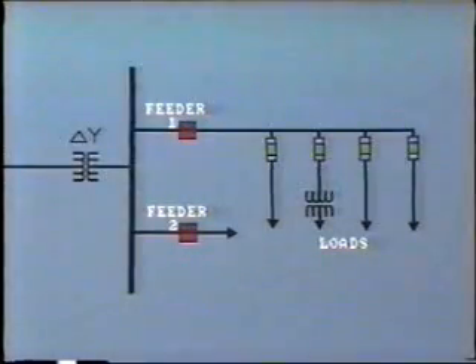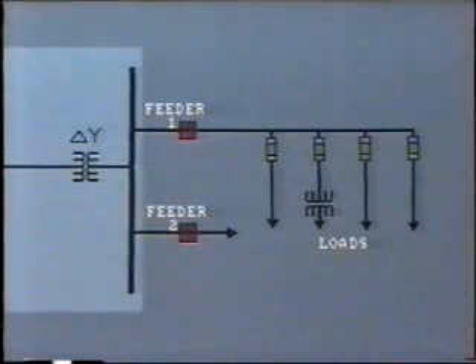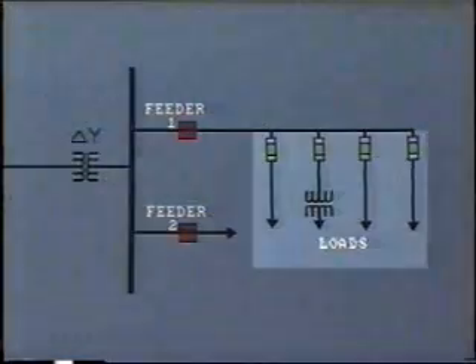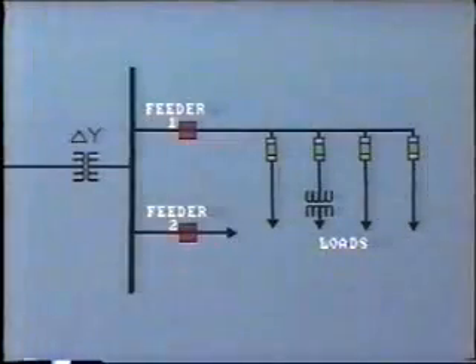By far, the most common way of operating a distribution line is by a radial connection, like this. The line is supplied from a source at one end only, and loads are tapped off to feed the customers all along the route. Current flow is in one direction only, even under fault conditions.